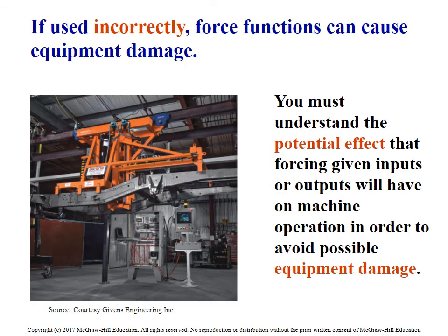And the last point I want to make, just to make sure that you're on board, is that when you enable forces, you let other people know in the shop. That way everybody is aware that there's forces keeping something running or overriding a potential problem, so it does get fixed. It's pretty common to have everyone forget that there's a problem after a force has been implemented, and then to have a machine fail because that input was overridden.